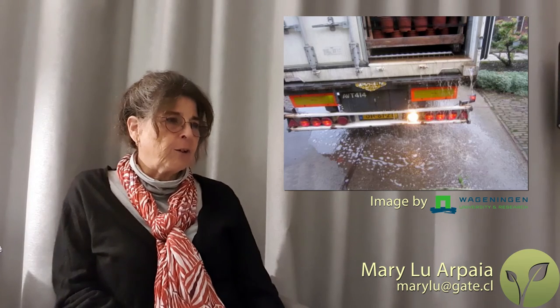Finally, when you looked at the container itself, what was the most interesting or little-known fact for you? I've been inside containers and looked at the T-bars, but what was most interesting was looking at the drain holes. Most people forget about drainage — you hear horror stories of opening the back of a container and water pouring out like Niagara Falls. What was emphasized is that when inspecting a container before loading, besides making sure it's clean and in good order, you need to make sure the drain holes are open, because the refrigeration process generates water.